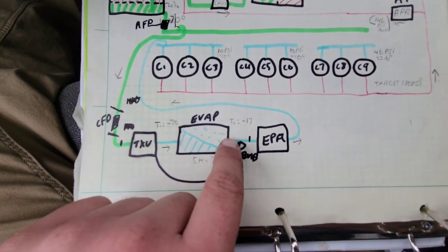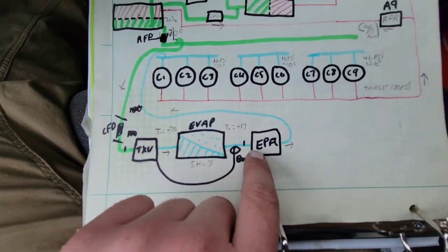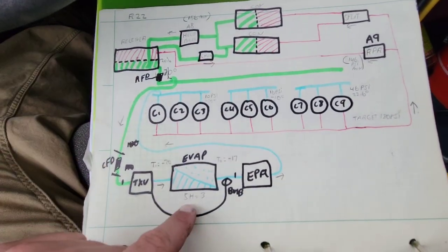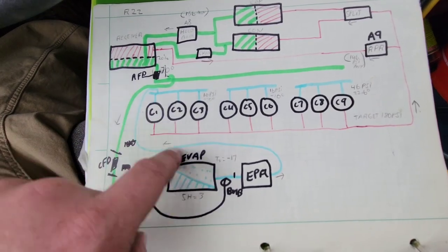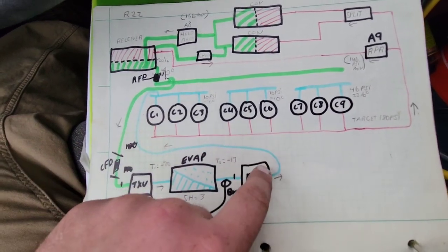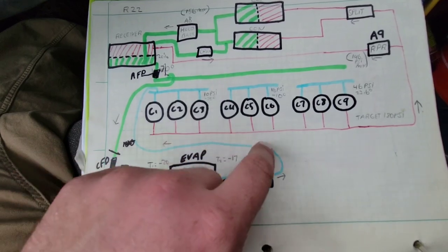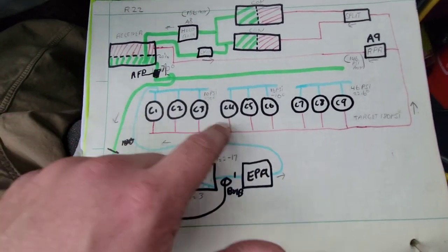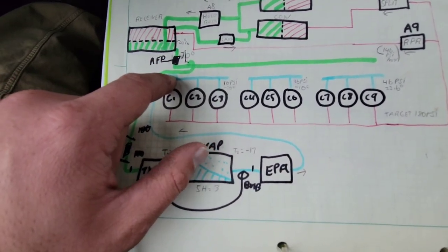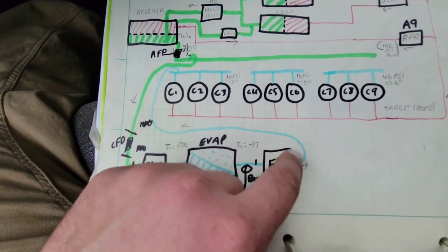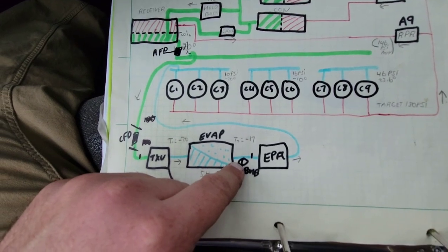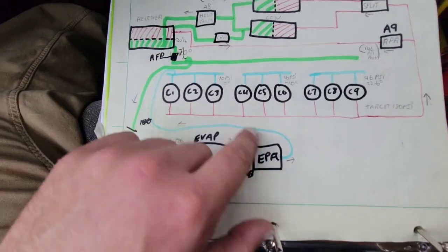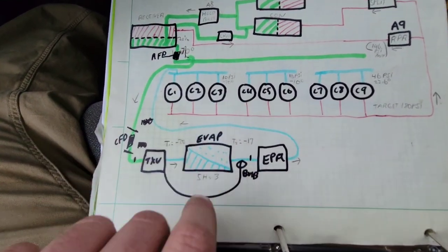And why would you want to check the pressure here at the case when you already checked the pressure up at the rack? Well, I actually dealt with a call where they added another case on a circuit when the line set was too small. So that line set had a pressure rise all the way over here. Right before the rack, the pressure was like 18, but at the case, the pressure was like 26. Why? Because the line size was not sized properly, causing this pressure differential, causing the case to run warm.